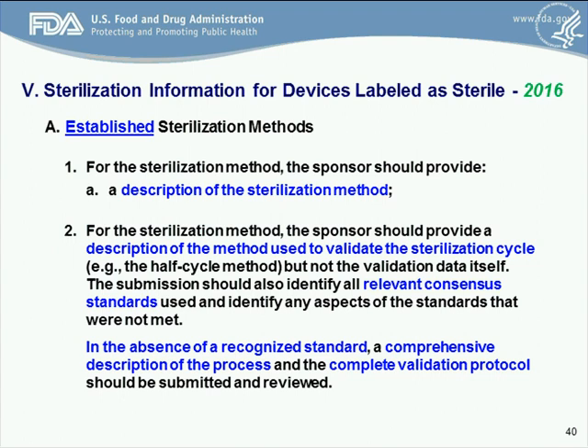Before jumping into the novel sterilization methods section, I'd like to revisit some text from earlier slides. For established methods A and B, we're looking for a description of the sterilization method, a description of the method used to validate the sterilization cycle, all relevant consensus standards, and in the absence of recognized standards, a comprehensive description of the process and the complete validation protocol.